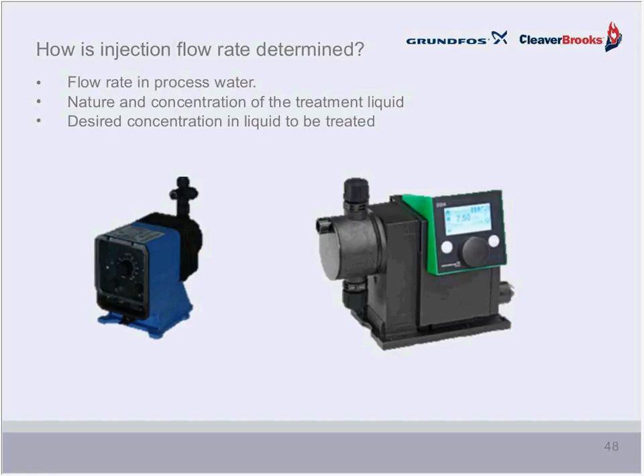So when a system designer is determining the appropriate flow rate of the metering pump, he or she works through a series of calculations based on the water or process steam flow rate, the chemicals that we will use for treating, and the resulting desired concentration level of the chemical in the treated liquid. These are really beyond the scope of today's webinar. Typically, the treatment company will advise based on the needs of the boiler system. I think we'll get into that more on next month's session.